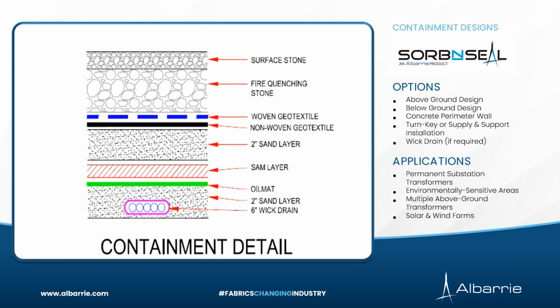So the other factor we need to consider is if the transformer has a catastrophic failure, the oil coming out of that transformer is going to be very hot. It could even be on fire. So we want to make sure that once it goes through those stones, it meets some resistance and it slows down that flow. What that does is allow the oil to cool down several degrees as it passes through this layer of sand, woven and non-woven, so that when it gets down to those reactive fabrics it is at a much lower temperature, and they can effectively work. Okay. So this amounts to about 5 inches in thickness for the actual system itself.